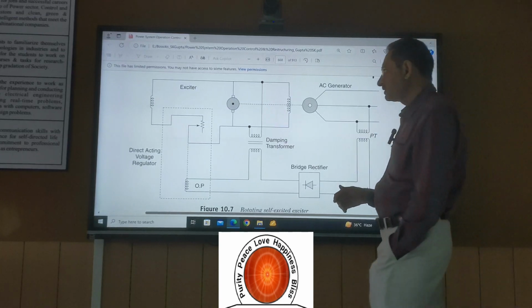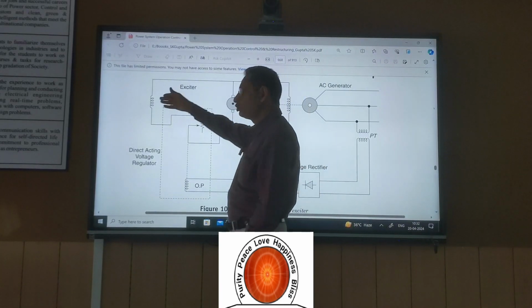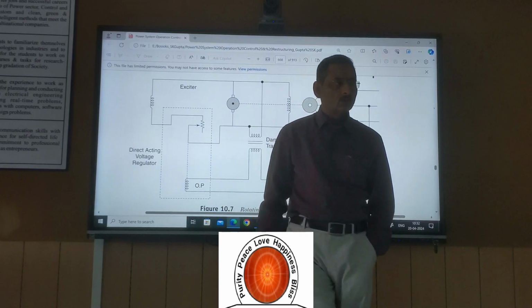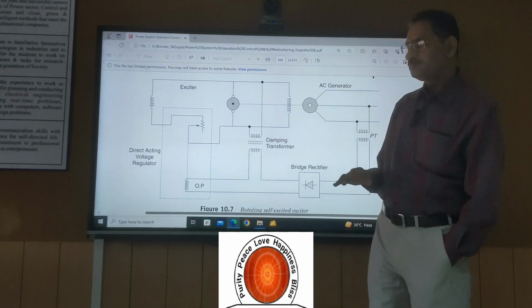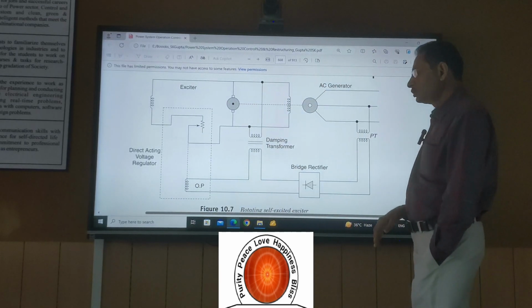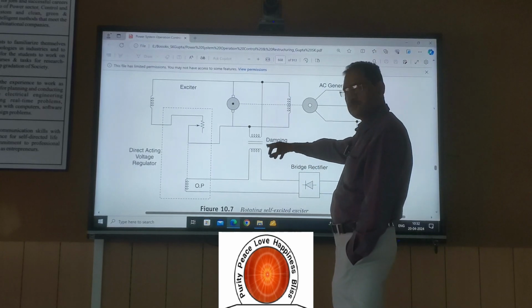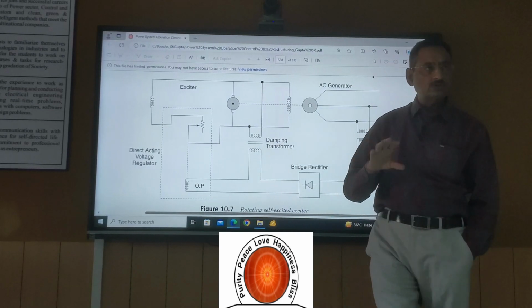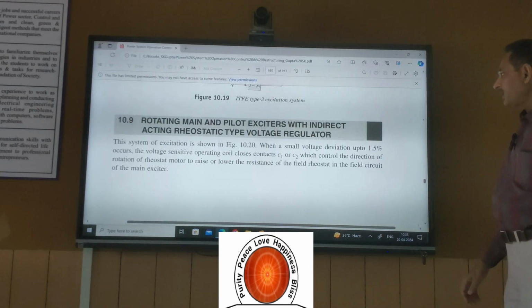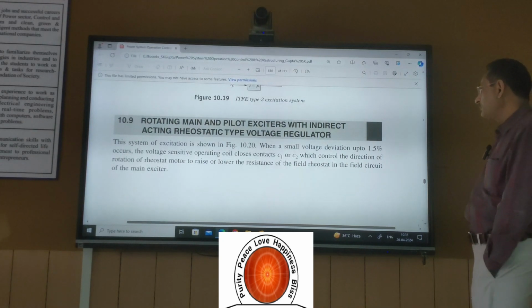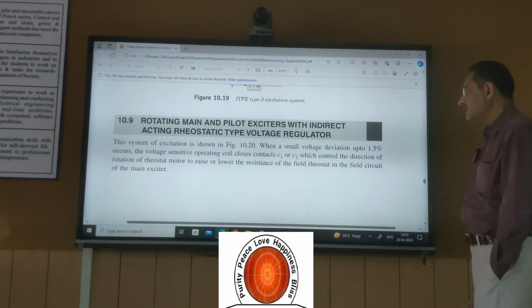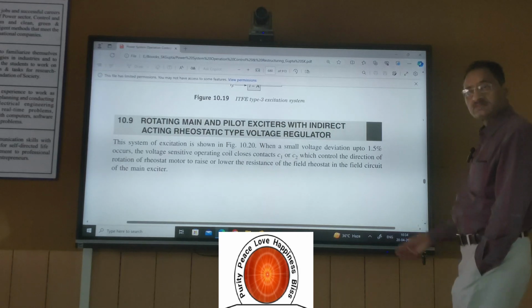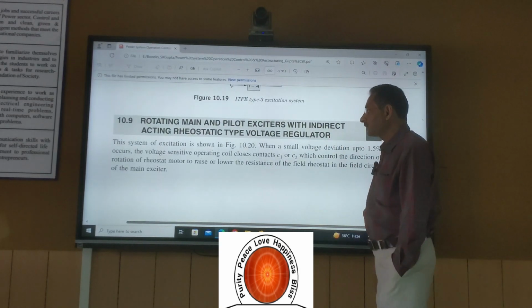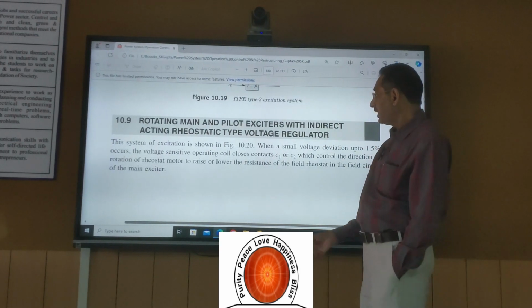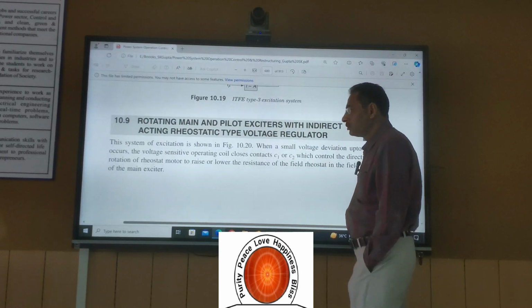Their frequency is defined by the value of inductance here. Now, to reduce that variation, the damping transformer is there. The damping transformer opposes the rotating main and pilot exciter. Rotating main and pilot exciter with indirect acting rheostatic type voltage regulator. That was the direct acting; this is the indirect acting type. And this is also rotating, rotating main and pilot both.